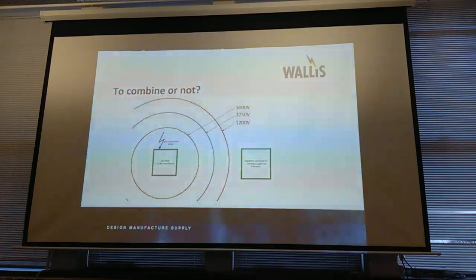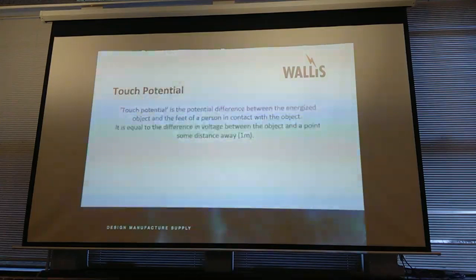Unfortunately, again, that is a little bit, we did a job up at one of the RAF bases in Lincolnshire. Because of the very long cable runs and the very small cables and very poor ground up there, we ended up having to have a 25 metre distance between the two systems, just because the rise of earth potential was high and the ground was poor. So it just goes to show that these standard values you get in a lot of these documents aren't always as good as they should be.